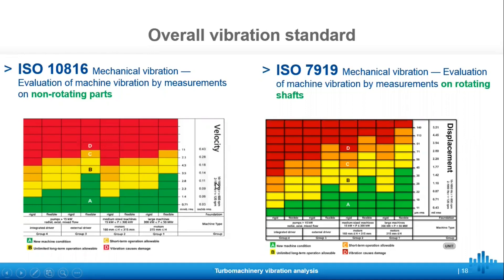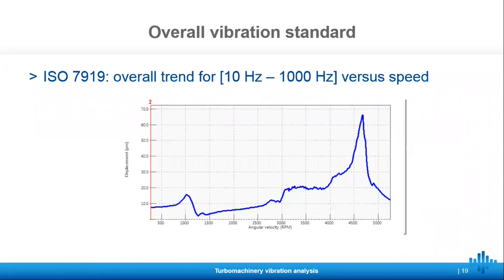For ISO 7919, the table is very similar — the bottom row with groups, machine type, and foundation are the same, and the frequency range is the same too. The one difference is that the y-axis now shows displacement, either in microns or mils, instead of velocity. These velocity and displacement values are easily calculated from your accelerometer data using the integration filters. You can also see an example of the overall trend of displacement from 10 to 1000 Hz plotted against rotation speed, which is the first relevant result we want to get from the turbo machinery at transient speeds.